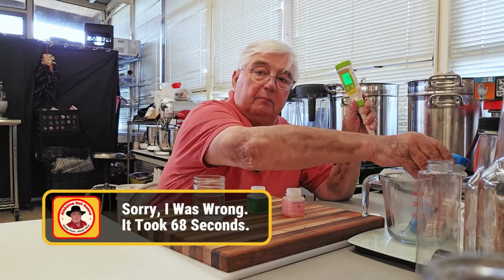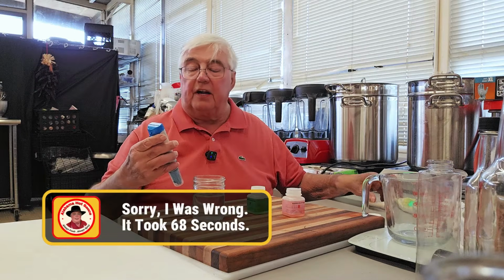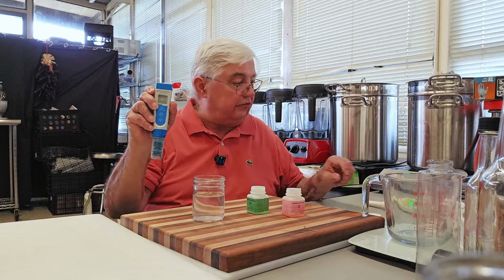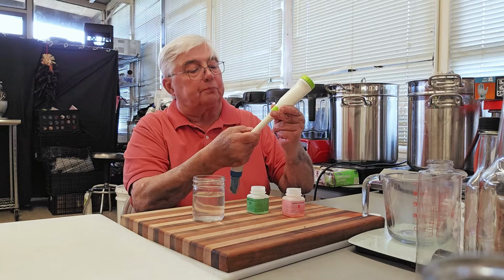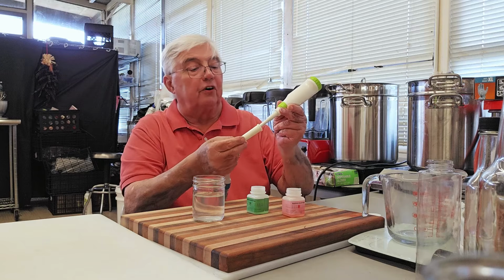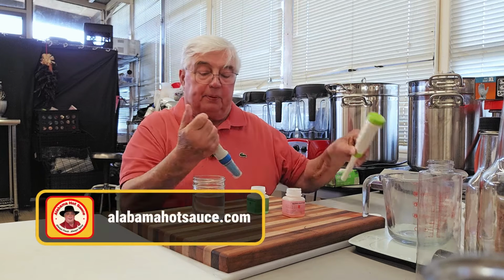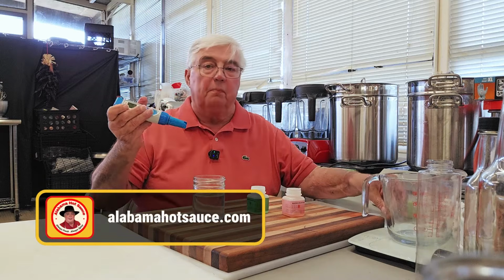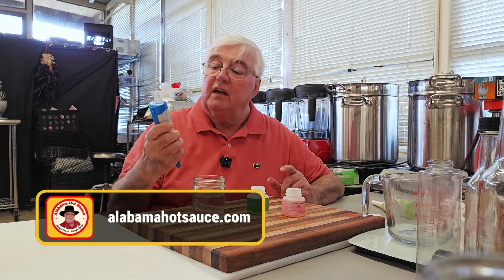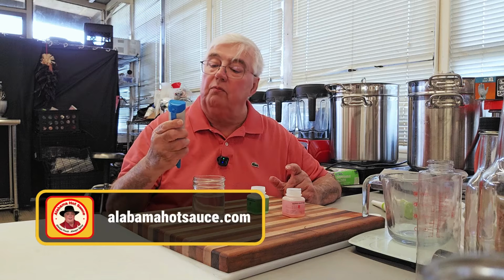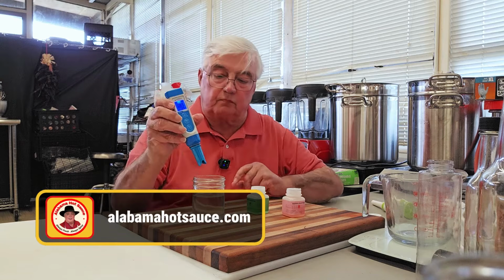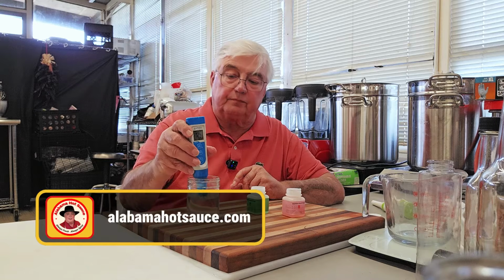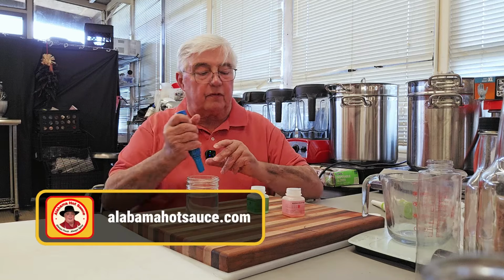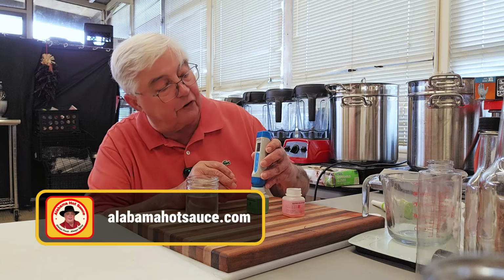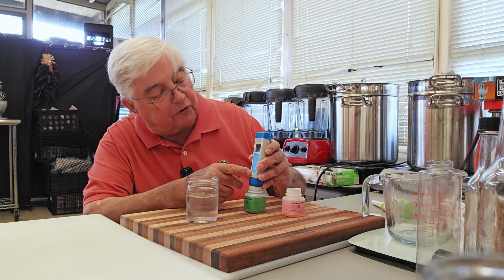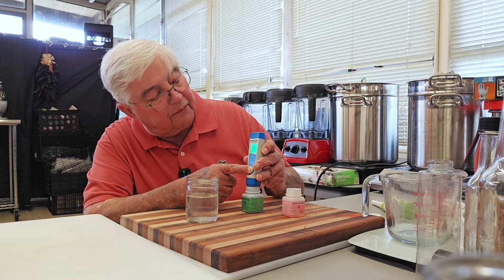Now, many people say, well, that don't work because I have an Apera meter. This is an Apera pH 60. It differs from this one. This is an exposed probe, which I absolutely prefer. And the Apera pH 50 is a hooded probe, but we do it the same way. I'm going to turn my machine on. As soon as you get your machine on, you slosh it around in your clear water, shake it to dry it. You always go to the 7.0 first. Once you get it in there, you let your number stabilize, and you press the calibration button.